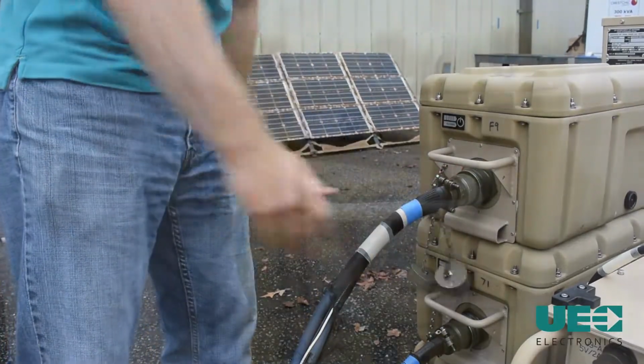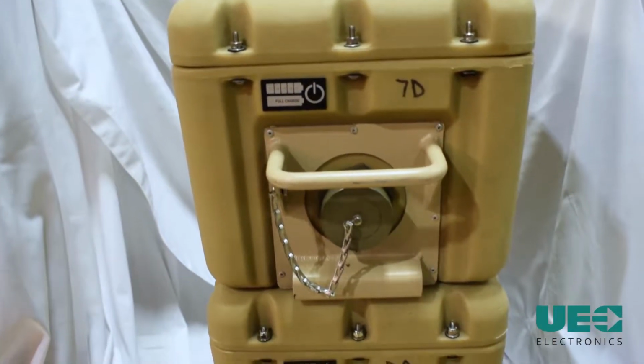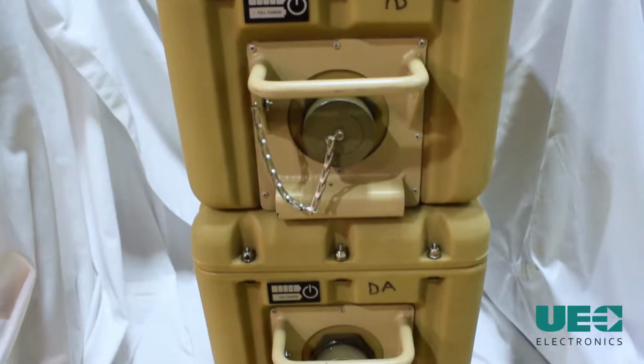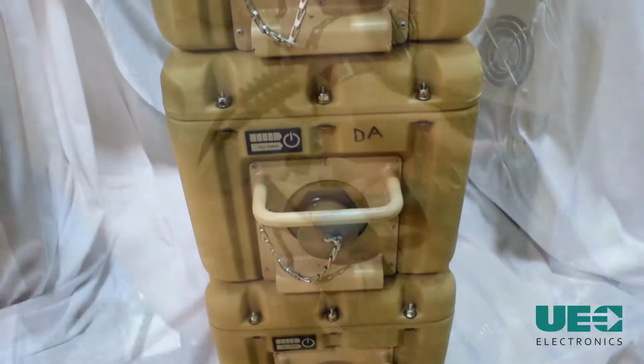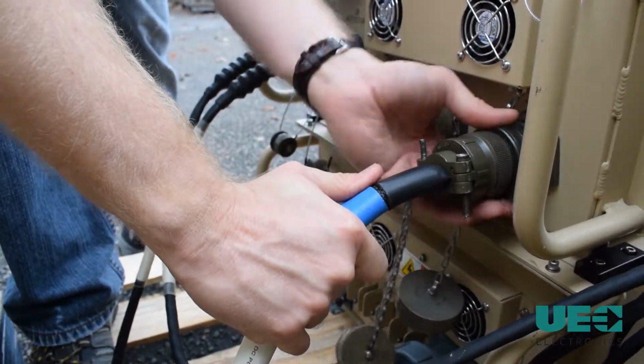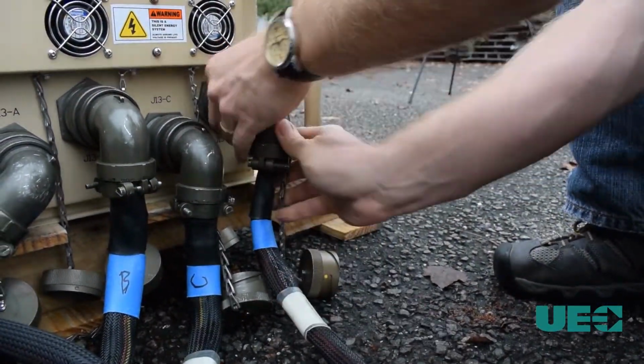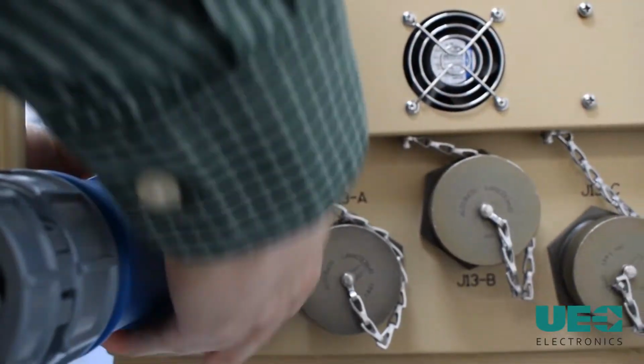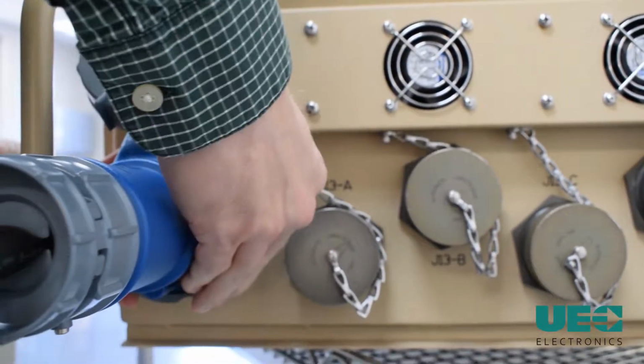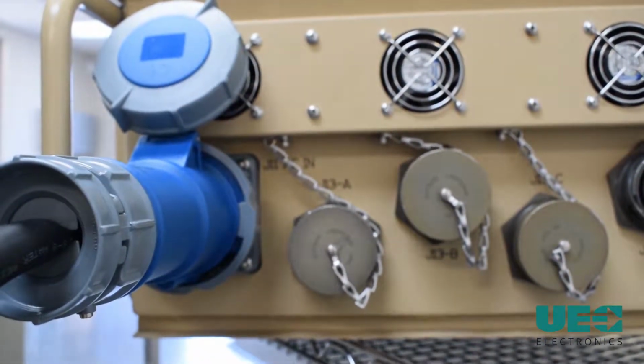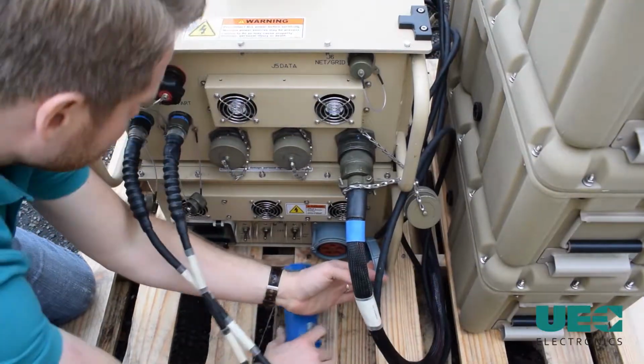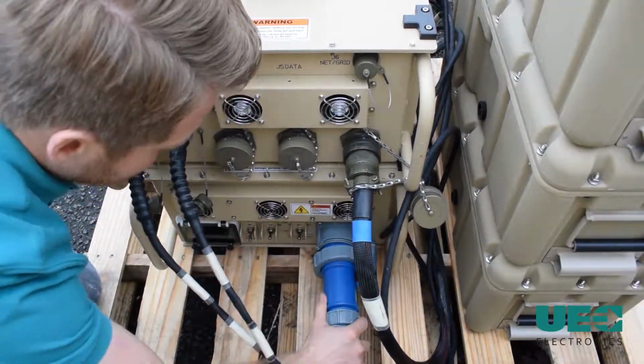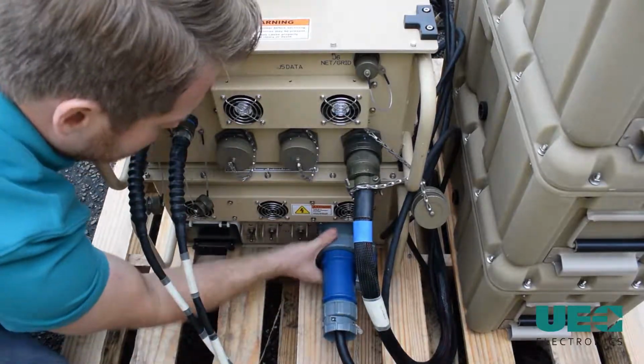The MEHPS Light can be connected to as many as 5 2,600 watt-hour large format batteries. After all batteries are connected, use a DC link cable to connect the DC PDU and the AC PDU. Connect the generator to the AC PDU via the J11 AC in port. Plug the load cable into the J12 AC out port on the AC PDU.